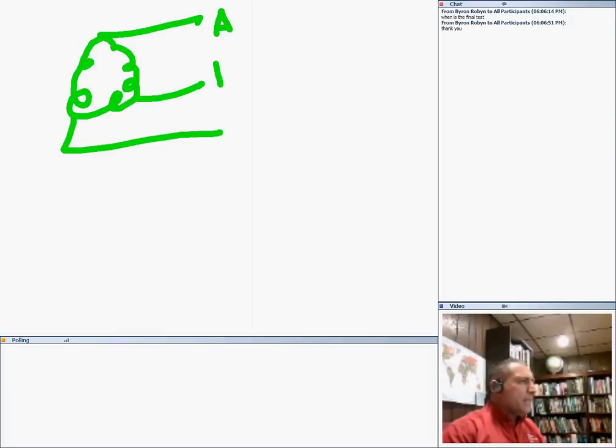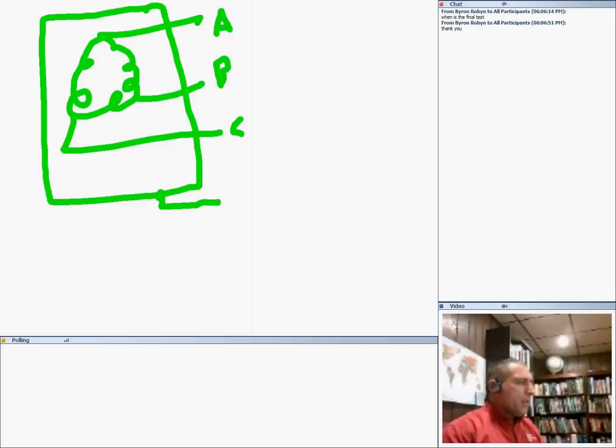For example, let me show you this. If you have a system like this, guys, and I always emphasize, a system grid, here's phase A, phase B, and phase C. Is this system grounded? And here's the frame, and the frame is going to the ground. Can you look at this and tell me, is this transformer grounded? Is this system grounded? There is a conductor here, right? The system is not grounded.